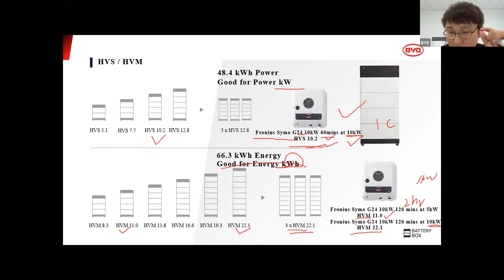Okay, a summary of the selling points I mentioned. It doesn't matter if it's single phase, 3-phase, on-grid, emergency backup, or off-grid. As long as the inverter supports off-grid, our battery supports that. But in the Australian market, there are no high voltage inverters that support pure off-grid. They can do emergency backup for a short period of time. They cannot do off-grid, and there's a big difference. Off-grid means no grid at all. They're running the battery system 24/7.